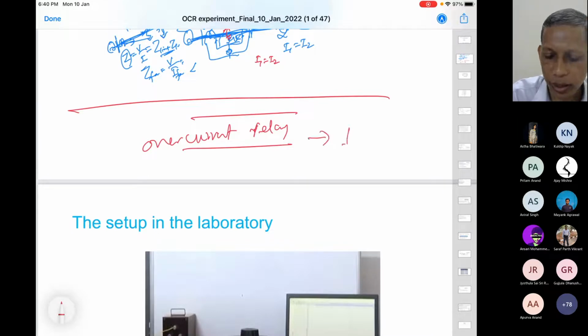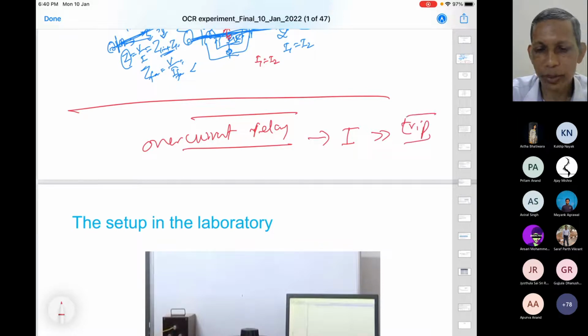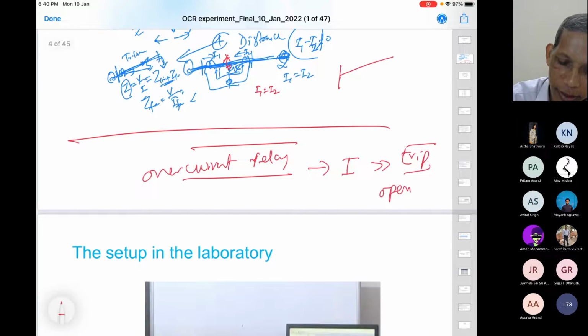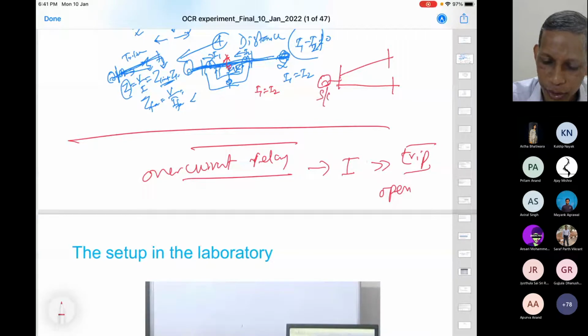As the name says, when I is high, it should command the breaker, we call it trip. It should issue a trip command to the breaker to open. That's all. But this judgment should be pretty good. One point I'll add here: let us say we have a system like this. From the substation, I'm putting a symbol of a synchronous generator. There is a substation there, and we have different lines coming out of it to transformer 1, transformer 2, load area 1, load area 2, and so on. Suppose a fault happens in this branch. Should this branch be affected? No.